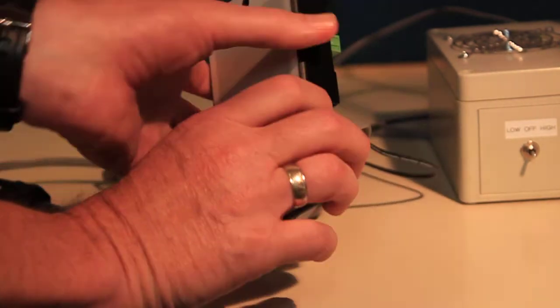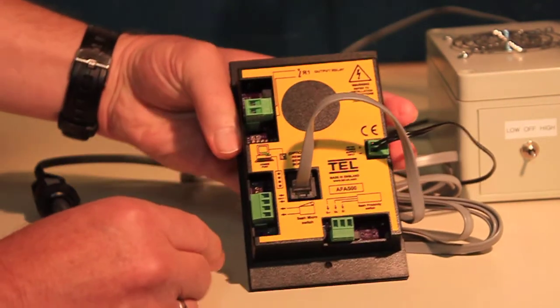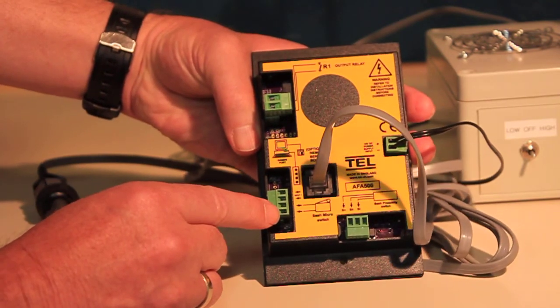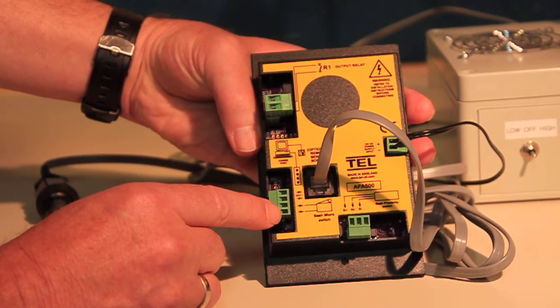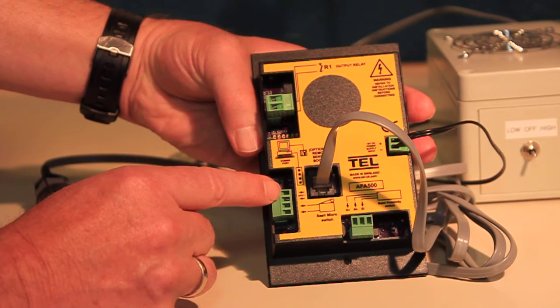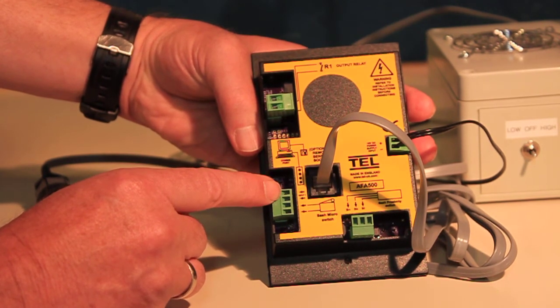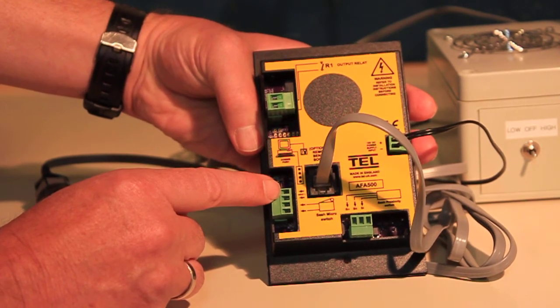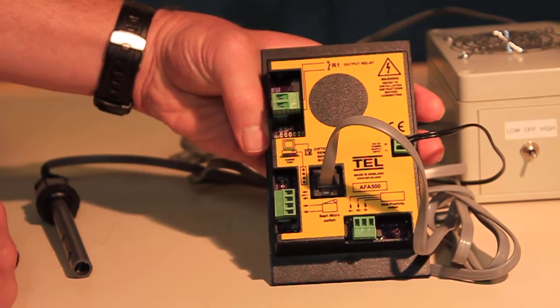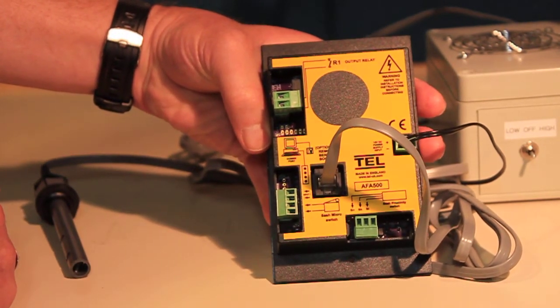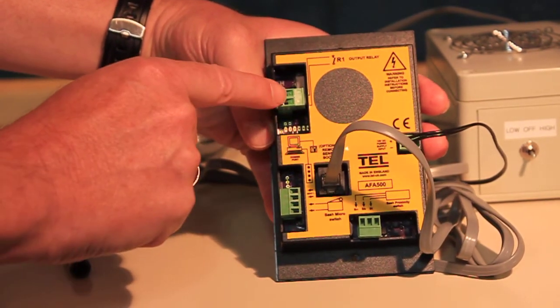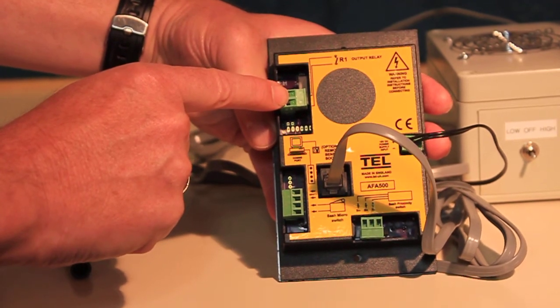The AFA 500 BSC has 2 relay inputs. One is for use with a micro switch that enables the alarm to sound if the visor is open past the set point. The second input is for night setback, which, through connection of external equipment to the volt-free dry contact relay input, mutes the audible alarm when the cabinet or room are set to an unoccupied state. The monitor also has a relay output that sends a signal to an external device whenever the unit is in alarm condition.